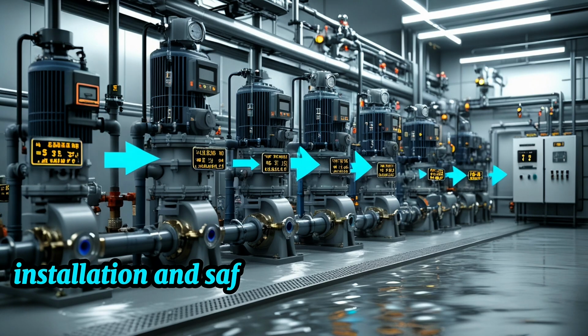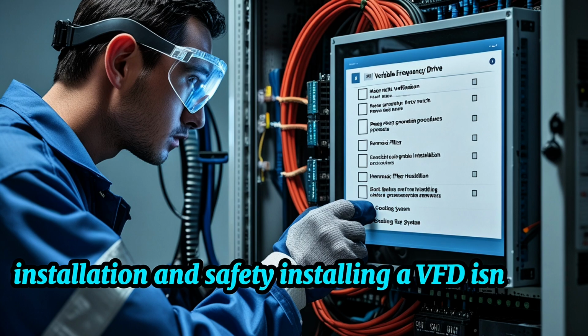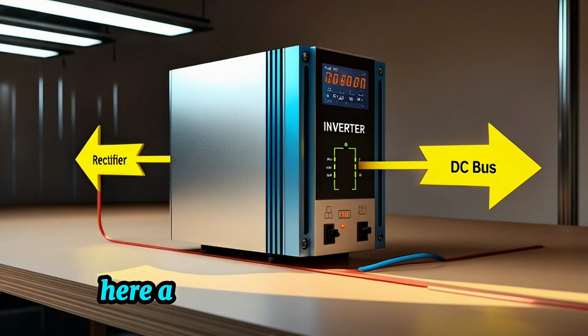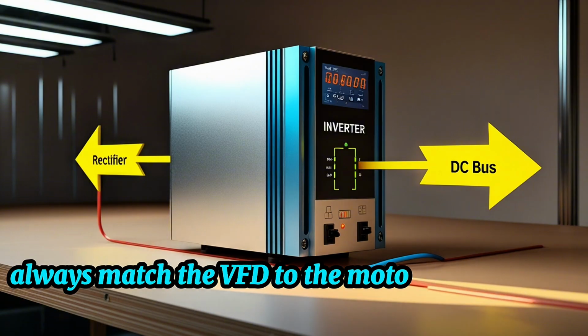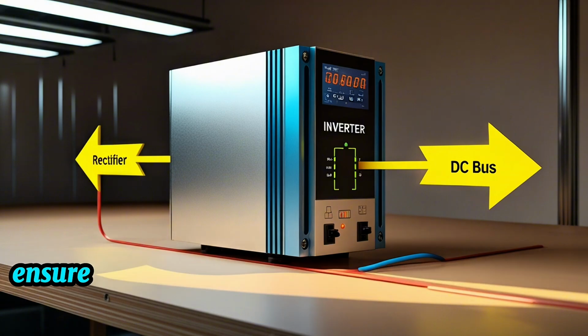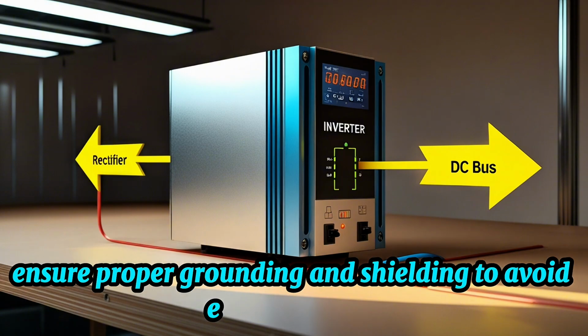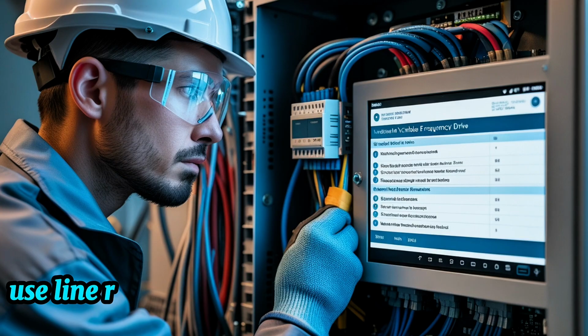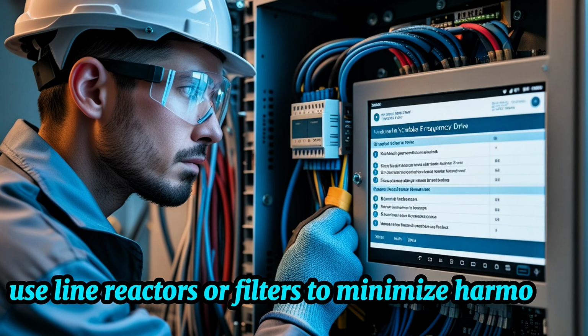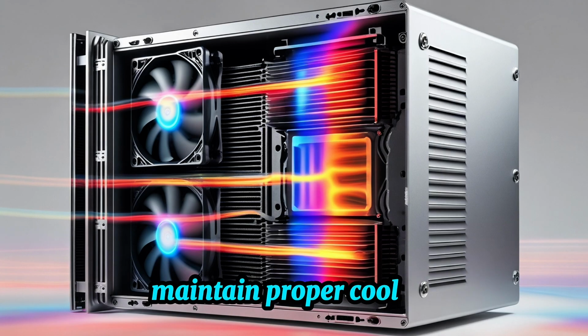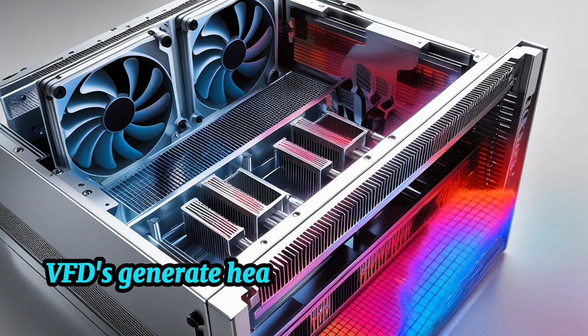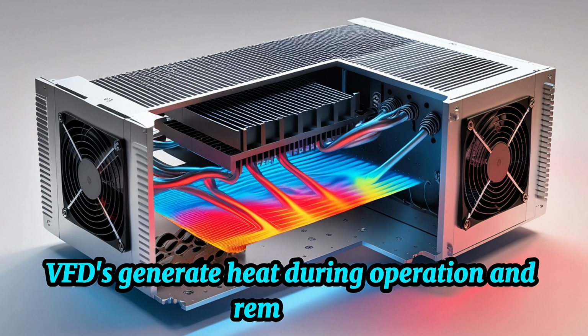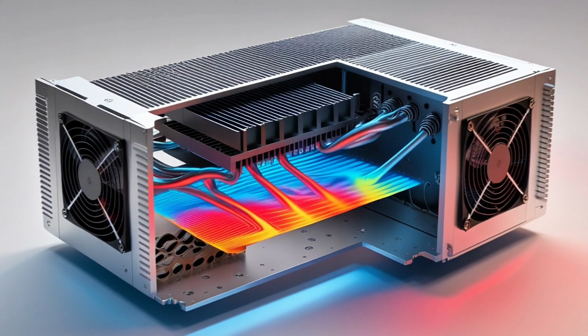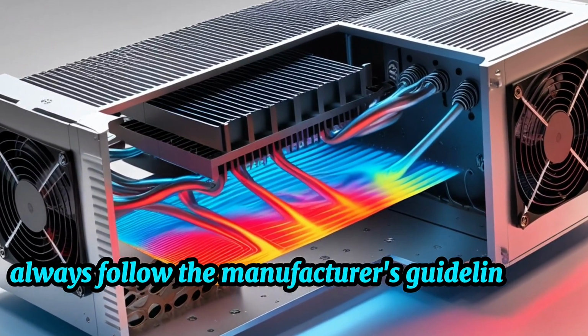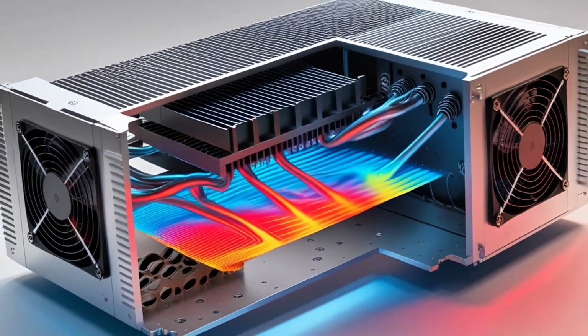Installation and safety. Installing a VFD isn't just plug and play. Here are a few key considerations. Always match the VFD to the motor size and load type. Ensure proper grounding and shielding to avoid electrical noise. Use line reactors or filters to minimize harmonics. Maintain proper cooling. VFDs generate heat during operation. And remember, safety is critical. Always follow the manufacturer's guidelines and local electrical codes.